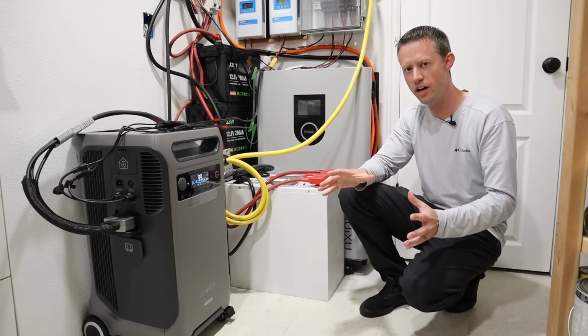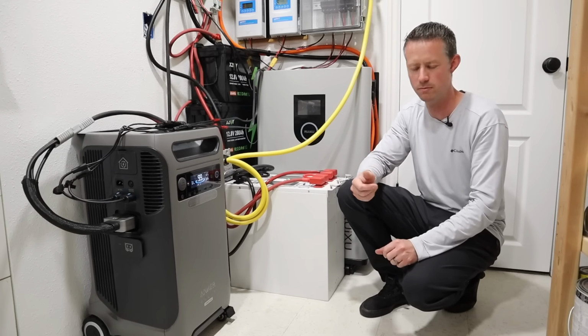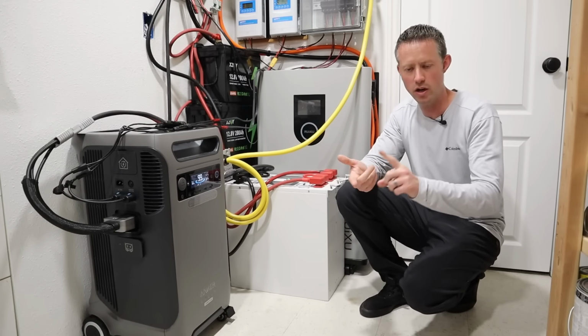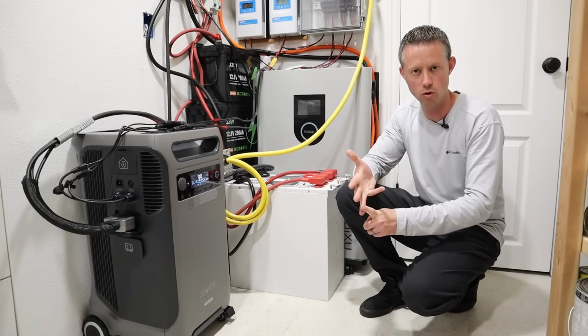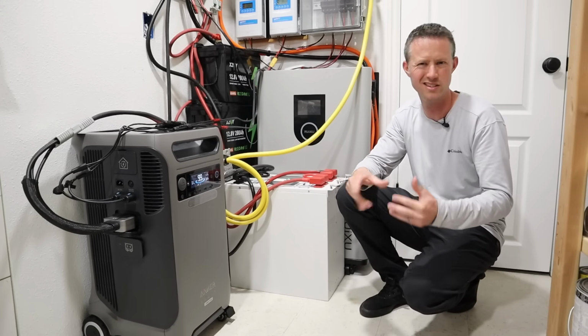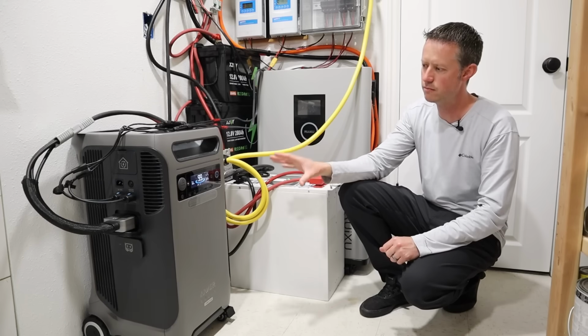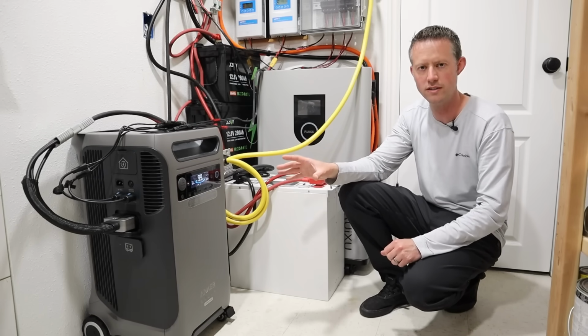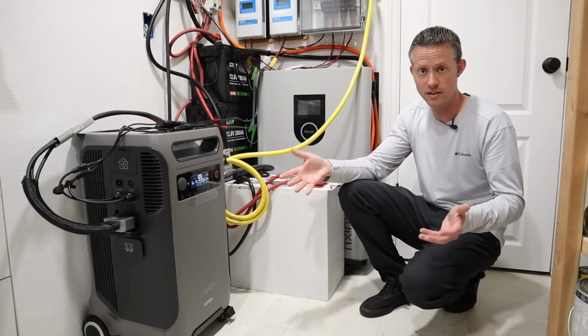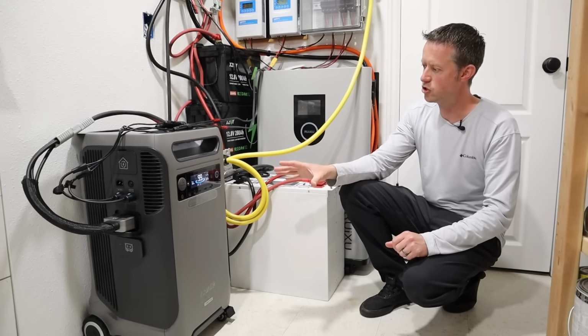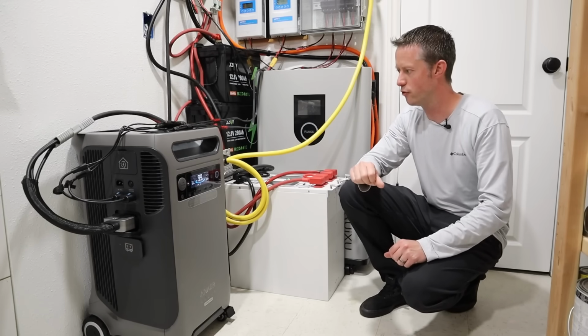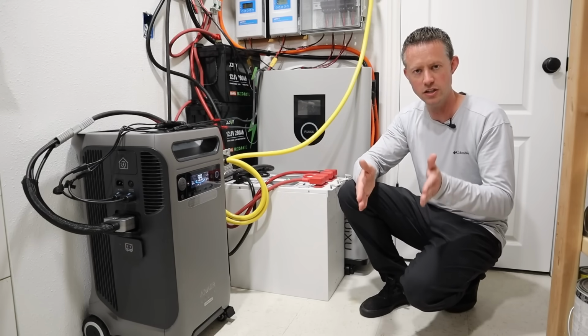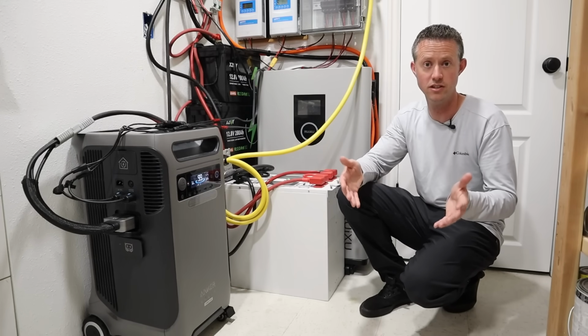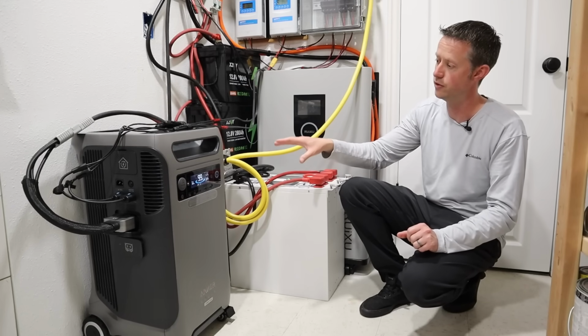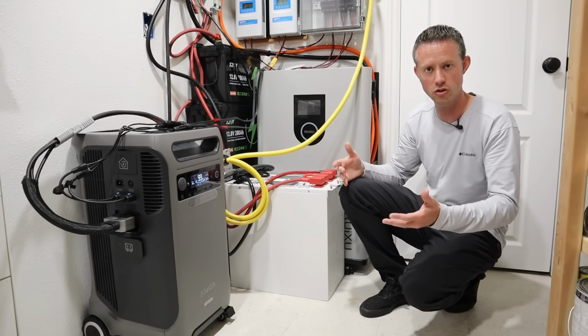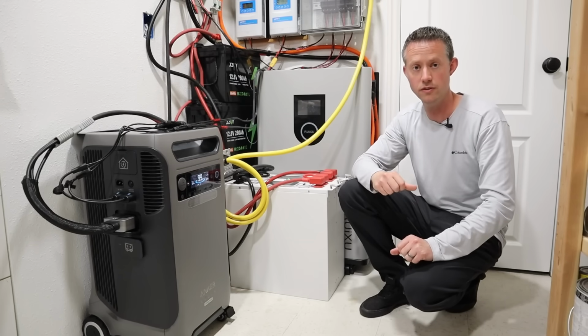Now, typically I'll have around 2,500 watts max because I really only run like a microwave or an air fryer or my garage door opener and just a few other electronics and lights and things like that. So this system doesn't really go over 2,500 watts, but if I was running multiple things at the same time, it would. You just want to make sure that with a 6,000 watt inverter, you have 3,000 watts on each phase. So you want to make sure that your phases don't go over 3,000 watts. You're going to overload the inverter. So you do have to kind of make sure that your inverter is built for the system that you're trying to run.